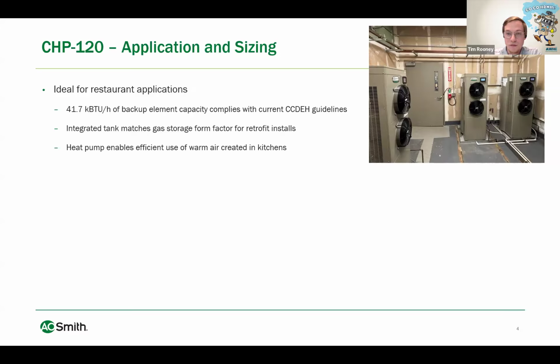Where jobs have mechanical rooms that are large enough to support the room volume requirements or airflow requirements, the form factor matches pretty closely to that of the existing gas tank products that these are often replacing. So it minimizes the amount of plumbing work that has to go in when a retrofit occurs. And then also, if there's some sort of airflow or communication with the kitchen air, the kitchen air is usually warm, and that helps increase the effectiveness of the heat pump.